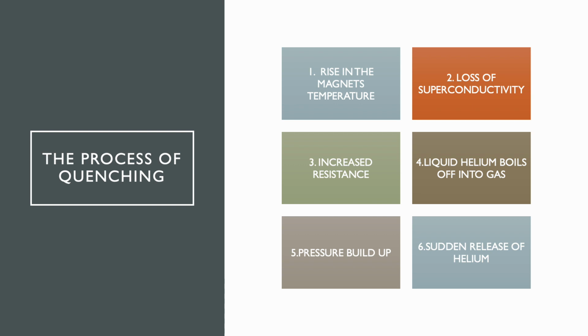A quench occurs when there is a rise in the magnet's temperature, resulting in a loss of superconductivity. This means that the resistance in the electrical current, as previously described, is no longer at zero, which results in a chain reaction. First comes the ever-increasing resistance, which causes more and more heat. The heat causes the liquid helium to boil into gas, and this causes the pressure to build up until there is a sudden, dramatic, and expensive release of the helium gas. Fortunately, all MRIs are equipped with a helium quench pipe, which vents it out of the building safely into the air.